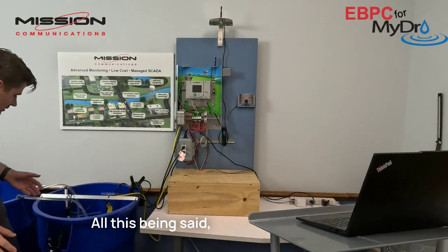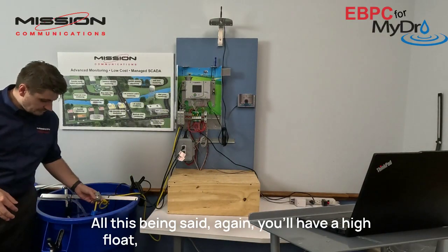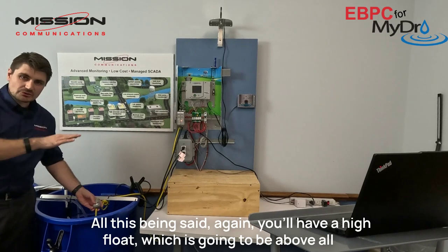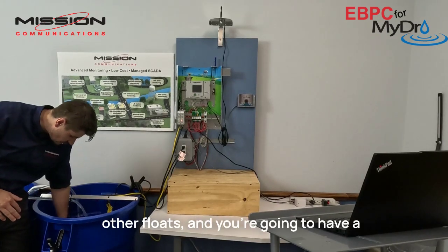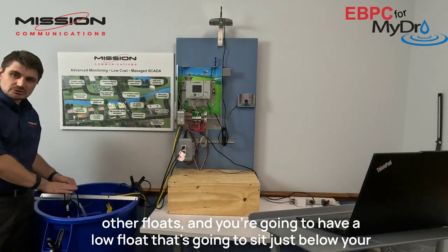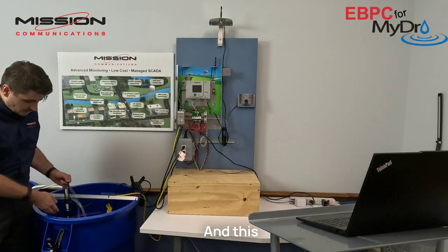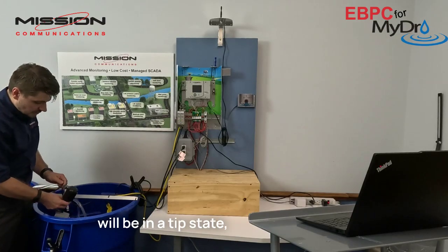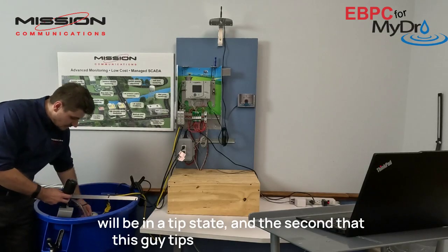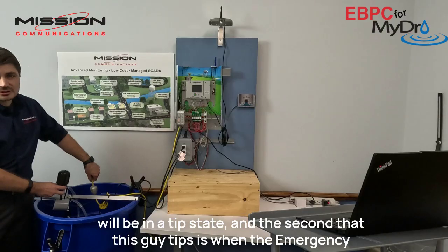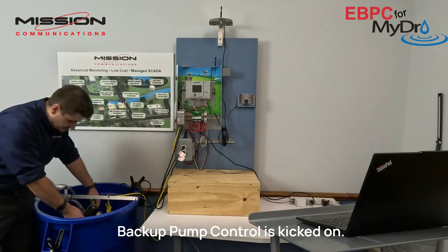All this being said, again, you'll have a high float, which is going to be above all the other floats. And you're going to have a low float that's going to sit just below your lowest floats. And this will be in a tip state. And the second that this guy tips is when the emergency backup pump control is kicked on.